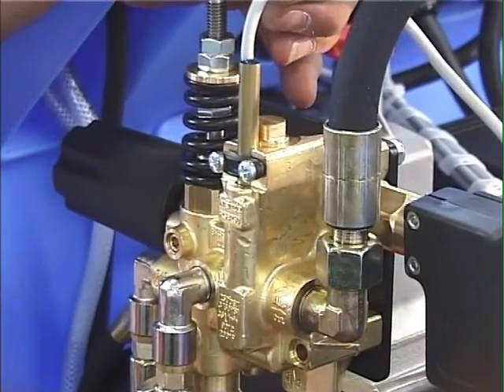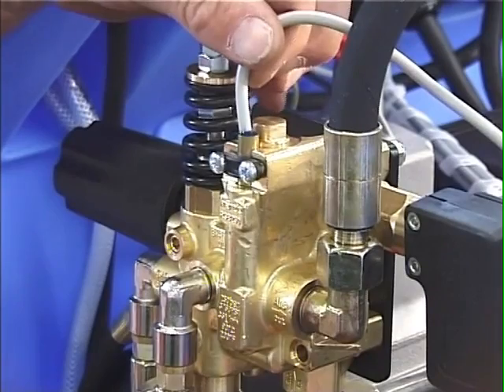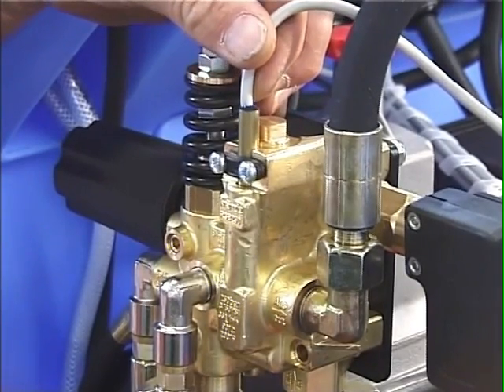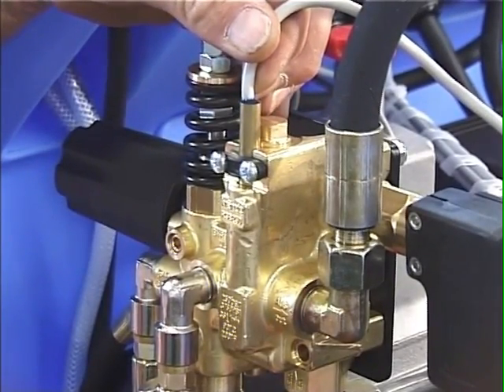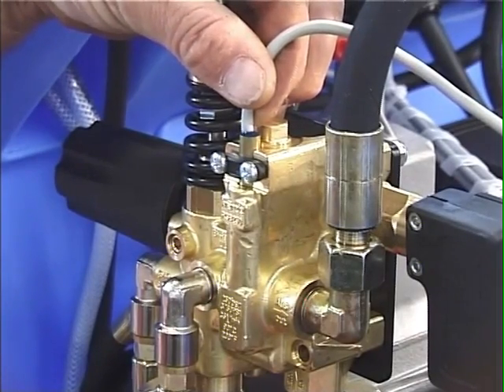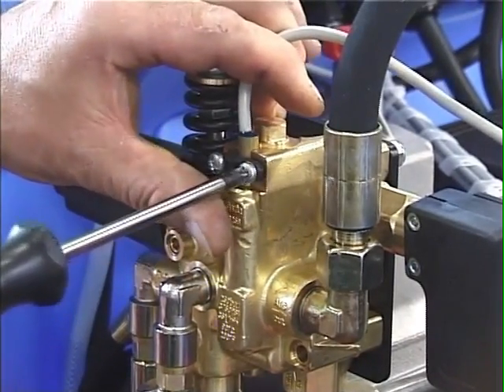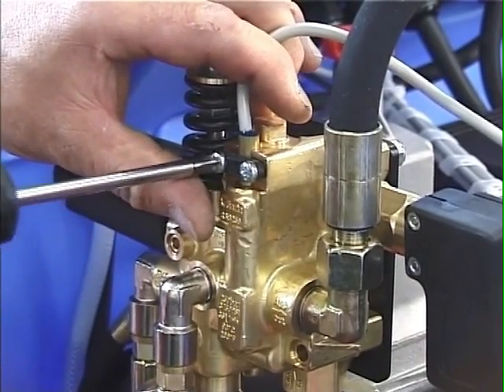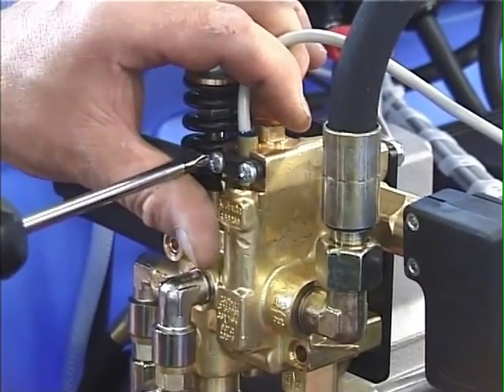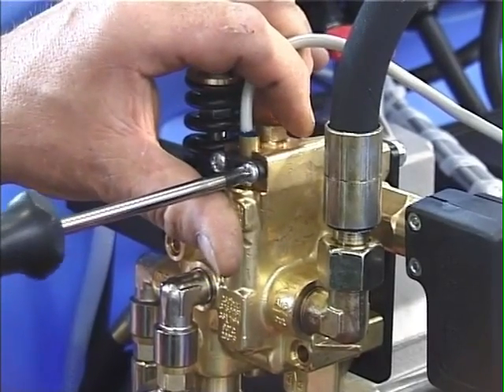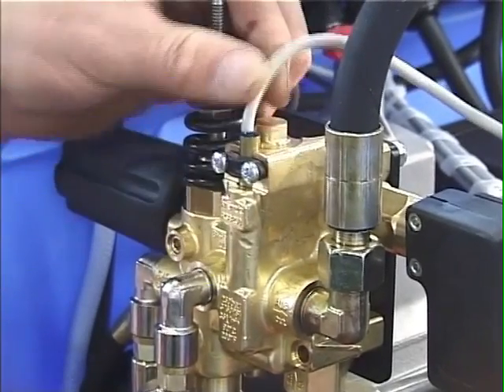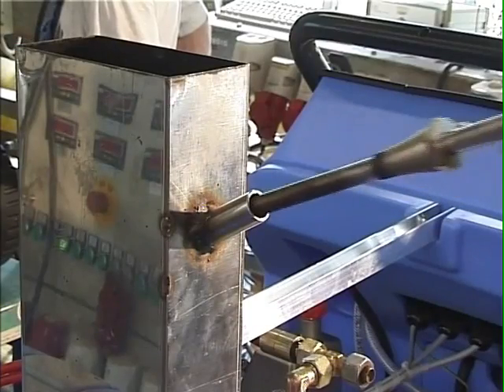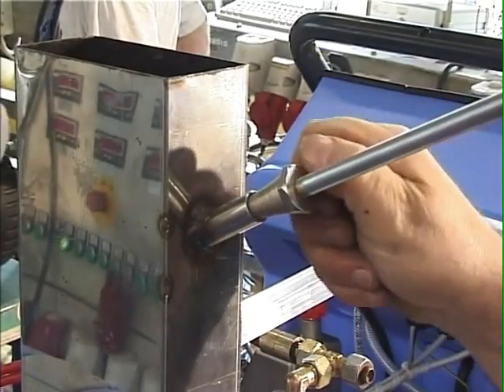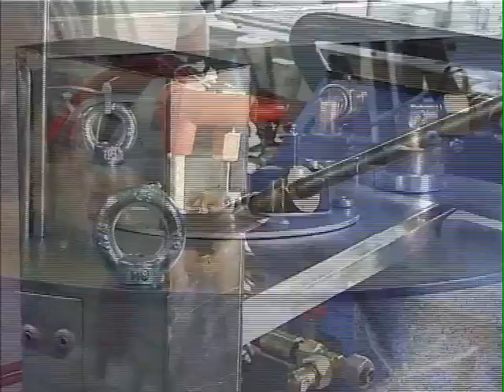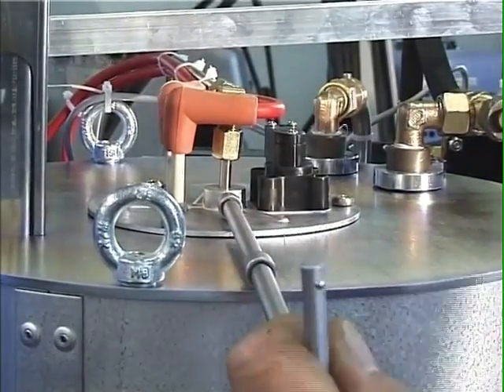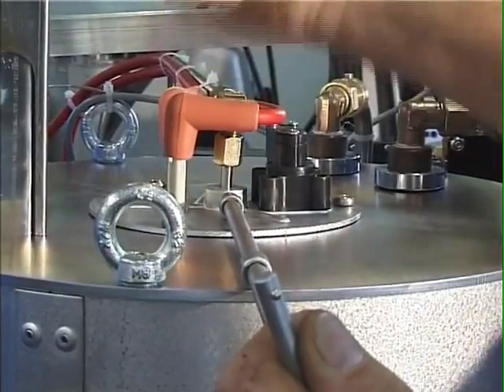The flow monitor is examined to see whether it has been switched off. Then it is fixed. In the case of C-series appliances, you must pay attention to the setting mark. A sensor for determining flue gas values is placed into the chimney. After that, CO and CO2 are manually finely adjusted on the nozzle stick.